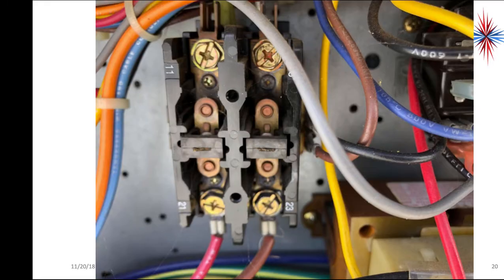Come over here, take a look at the contactor on the left. Okay, this is my indoor blower motor contactor. Okay, it is severely burnt, and again, this is wear and tear related. This is not voltage surge. You'll notice that there's 2 wires. There's no wires on the left-hand terminals of this contactor. Unfortunately, I didn't get a picture of that angle.